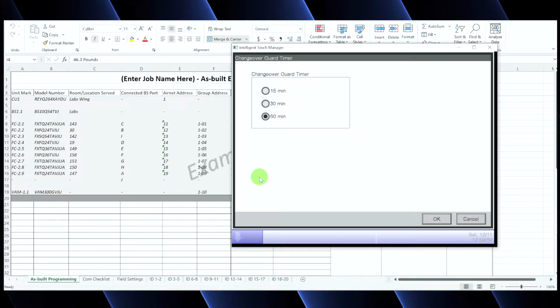And this is going to be the guard timer. If you recall from the nav controller series, I'll put a card in the corner now for you guys. The guard timer is the amount of time it takes once the room temperature has gone past the changeover temperature deadband before it'll actually switch modes of operation. So depending on how you're going to set up auto, whether you're going to have a really tight deadband or a wide deadband, and depending on if you're going to be using single set point or dual set point, that is going to dictate how fast you change over.